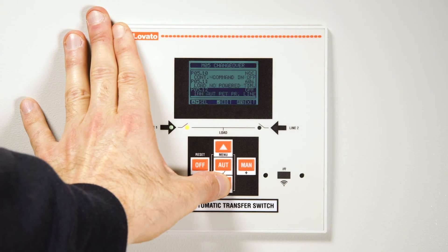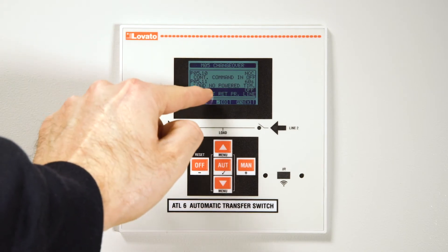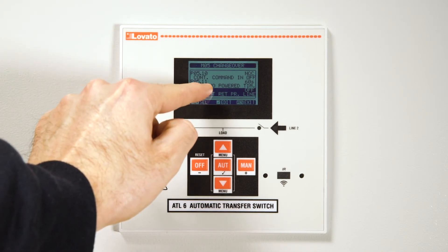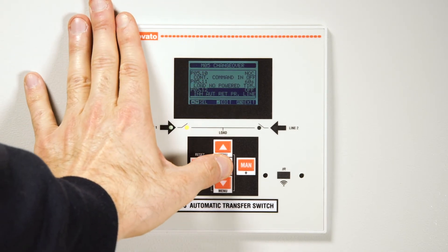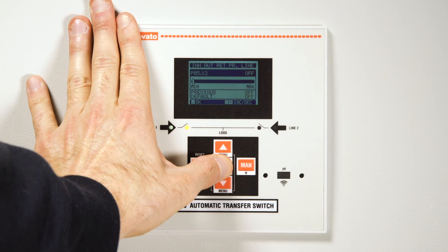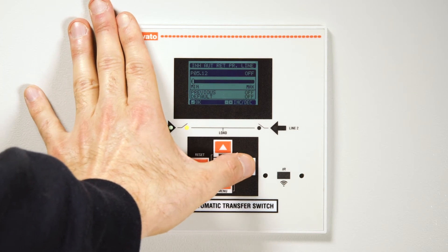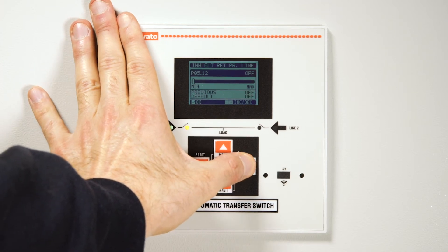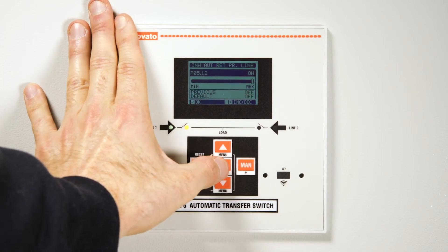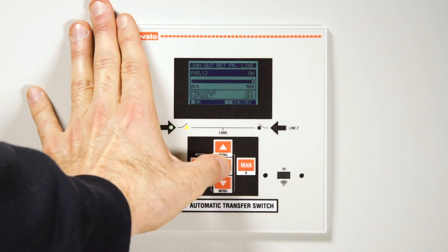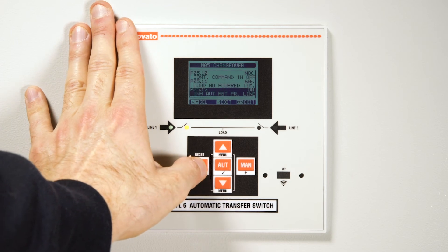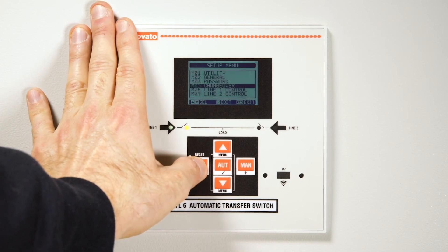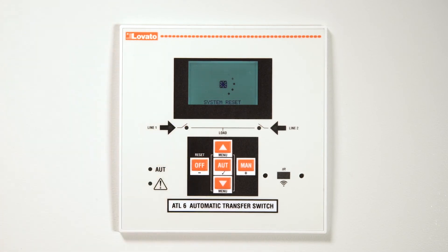In P0512, you can choose to prevent a return to the main line when it becomes available. This can be useful when you want to avoid a second power failure — for example, for applications involving two transformers. In this case, set the parameter to ON.